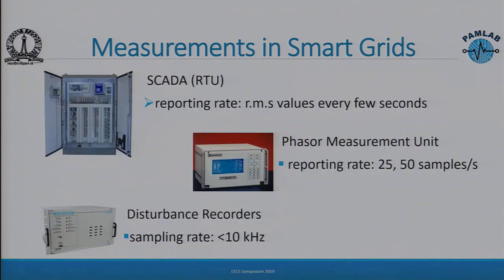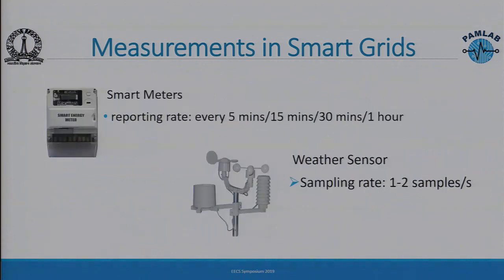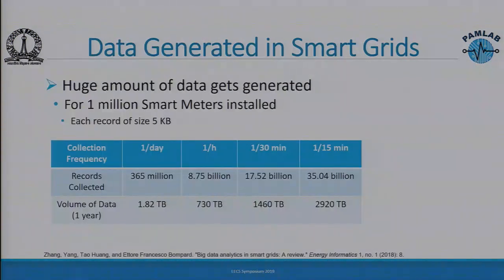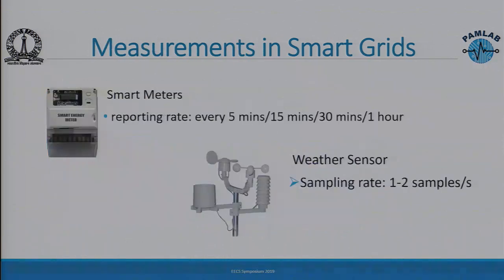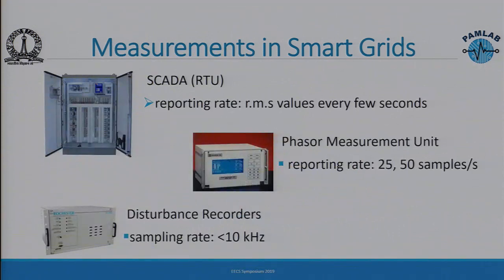Disturbance recorders log information whenever there is a fault, at a sampling rate of less than 10 kHz. Smart meters report every 5, 15, 30, or 60 minutes. Due to renewables we also have weather sensors sampling at 1 to 2 samples per second. All these sensors throughout the country are constantly generating data. For just 1 million smart meters reporting every 15 minutes, the data volume is 2920 terabytes per year — and that is just smart meters, not counting SCADA, PMUs, and disturbance recorders.